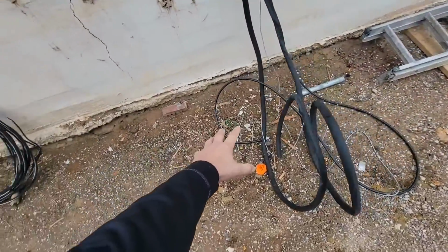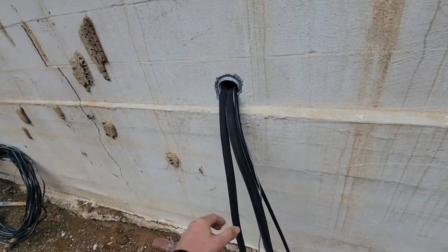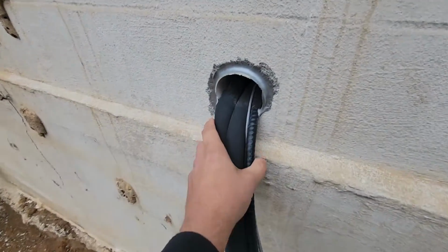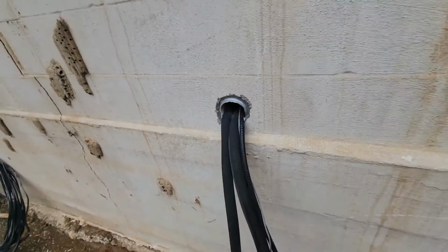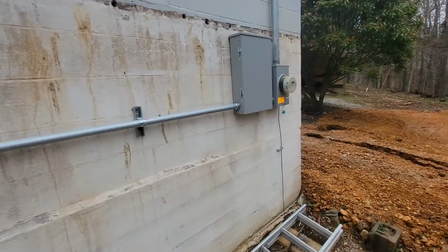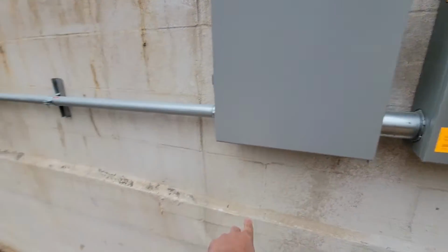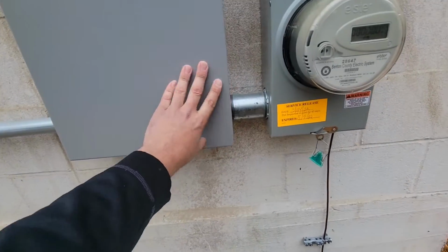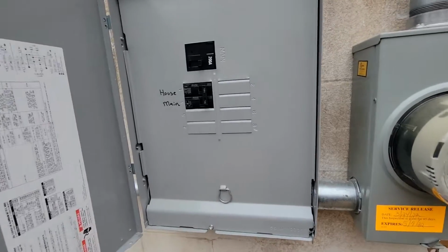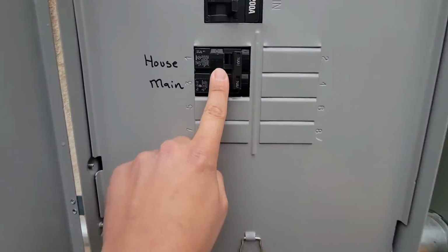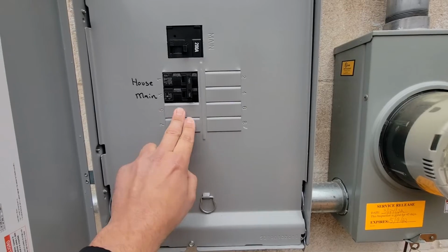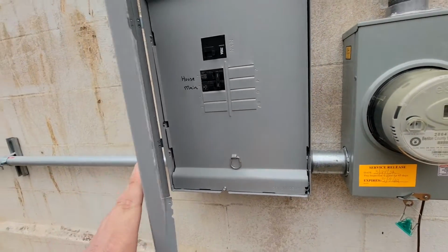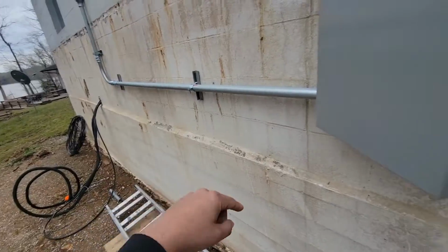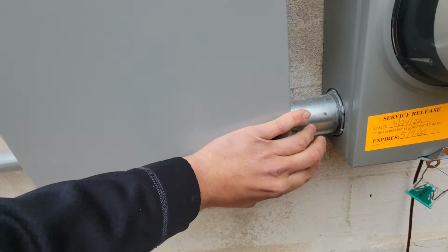So we're ready to install the outdoor and the indoor unit. Let's take a look at the progress. This is where our outdoor unit is going to be, and this is where our line sets come from the indoor to the outdoor. Looks like they got some 3-inch PVC here. That is nice. This is our outdoor breaker box, so we'll run conduit from the outdoor unit to this box, and then there is a place for a breaker here. So we got 100 amp for the house, and then we'll have a double pole, probably a 20 breaker for that 1 ton unit. It's going to have a number 12 wire, 12-2, and that should be perfect.